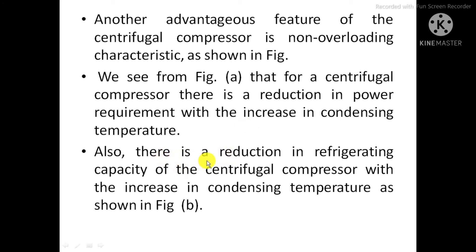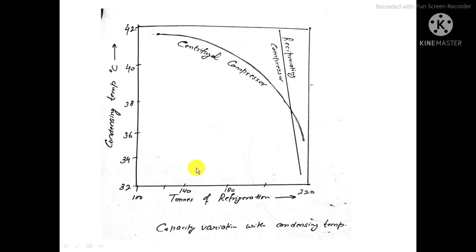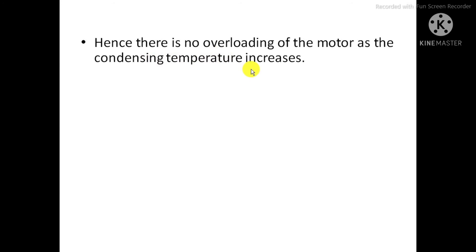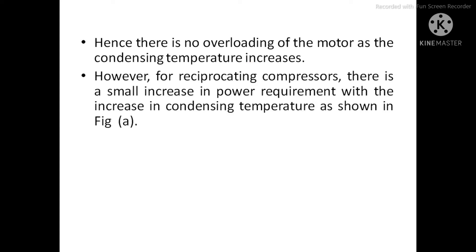There is also a reduction in refrigerating capacity of the centrifugal compressor with increase in condensing temperature, as shown in figure B. In this diagram the x-axis shows tons of refrigeration capacity and the y-axis shows condensing temperature. When we increase the condensing temperature, the refrigeration capacity decreases in centrifugal compressors. Hence, there is no overloading of the motor as condensing temperature increases, since the power requirement is less.